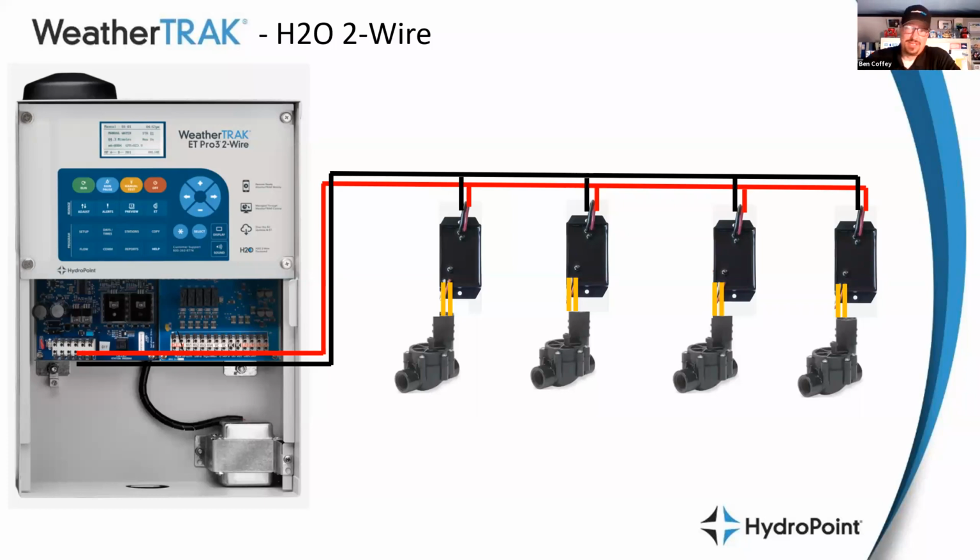And what we see, and we talked about in our troubleshooting episode, is issues with wire splices are by far the most common issue that we see with 2-wire. So by all means, if you're listening and you're considering 2-wire for the first time, definitely make sure that you have someone with 2-wire experience help you go through the installation process, because there is a very valuable tool that allows us to strip those wires without causing any sort of exposed copper that can be the long-term demise of that 2-wire path, right? That will cause you to come out and have to troubleshoot.